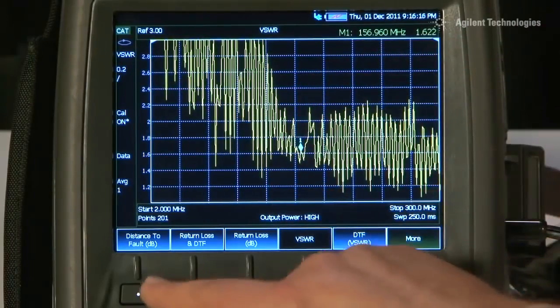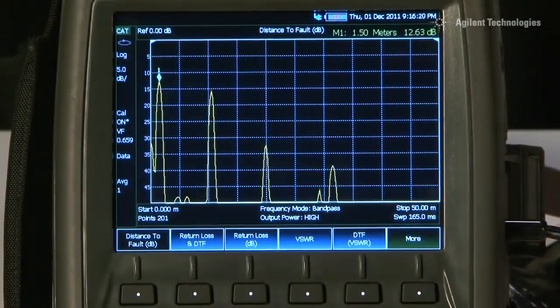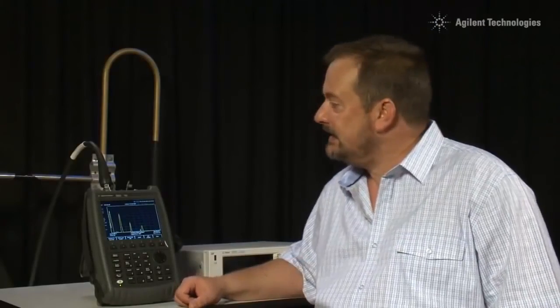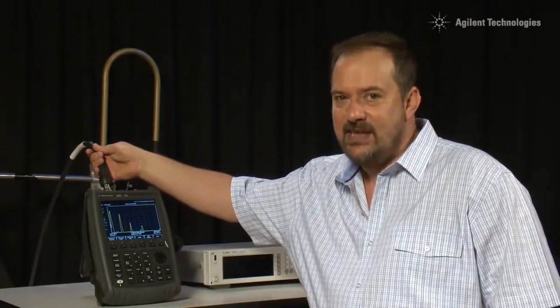And, if I look at the Distance to Fault, we can see why we are getting multiple reflections from various points down the cable. So how do we go about identifying whether it is the cable or the antenna that are at fault? Well, let us remove the cable from the measuring system and let us connect our fly lead directly to the antenna.